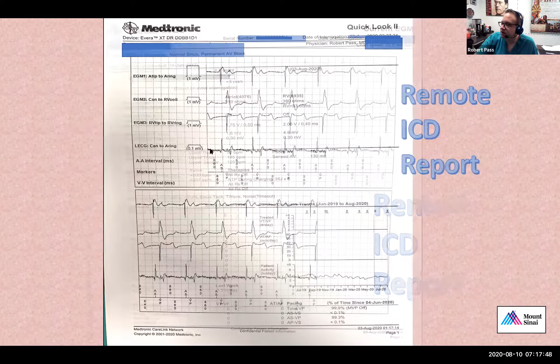In this case, the patient is programmed DDD with a minimum rate of 50 and upper tracking rate of 145. And here are the paced and sensed AV intervals corresponding to the PR interval. And then here we can see how I have programmed the pacemaker. Essentially, what I have told the device is that if the rate in the atrium or in the ventricle exceeds 200 beats per minute, I wanted to monitor it, which means I wanted to record it, but not deliver any therapy. You see, it says here, all therapy is off.